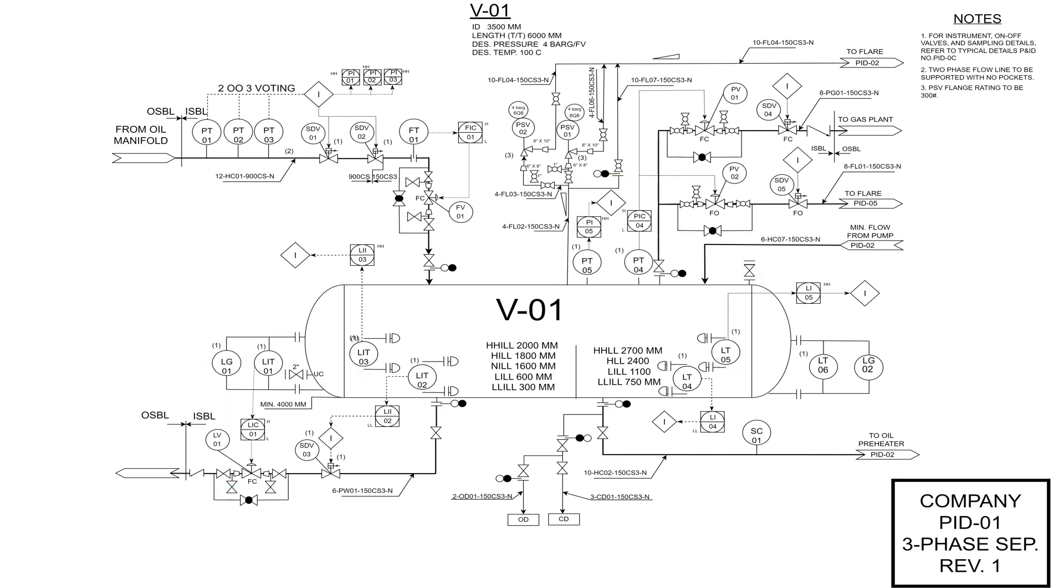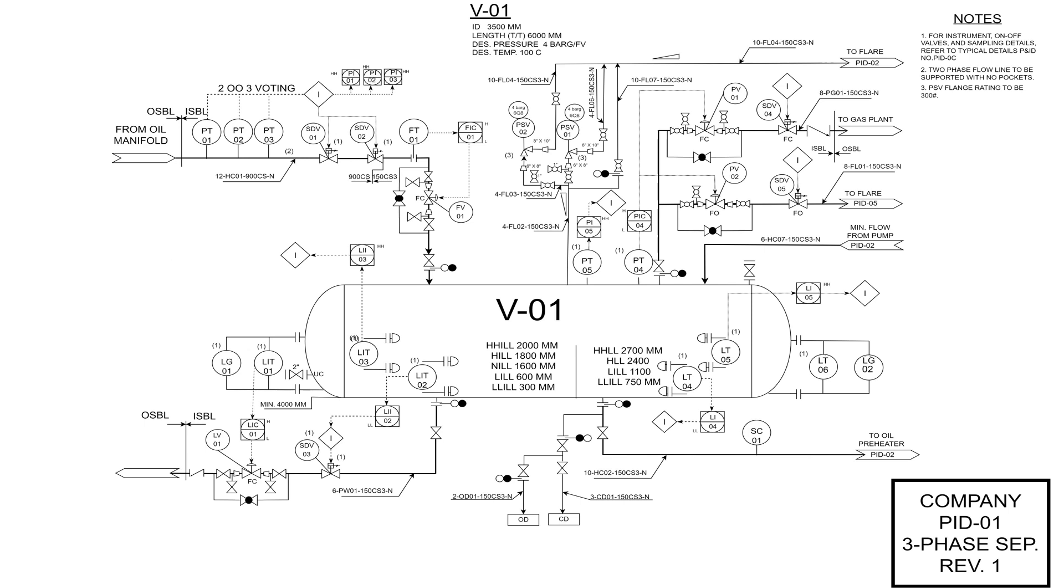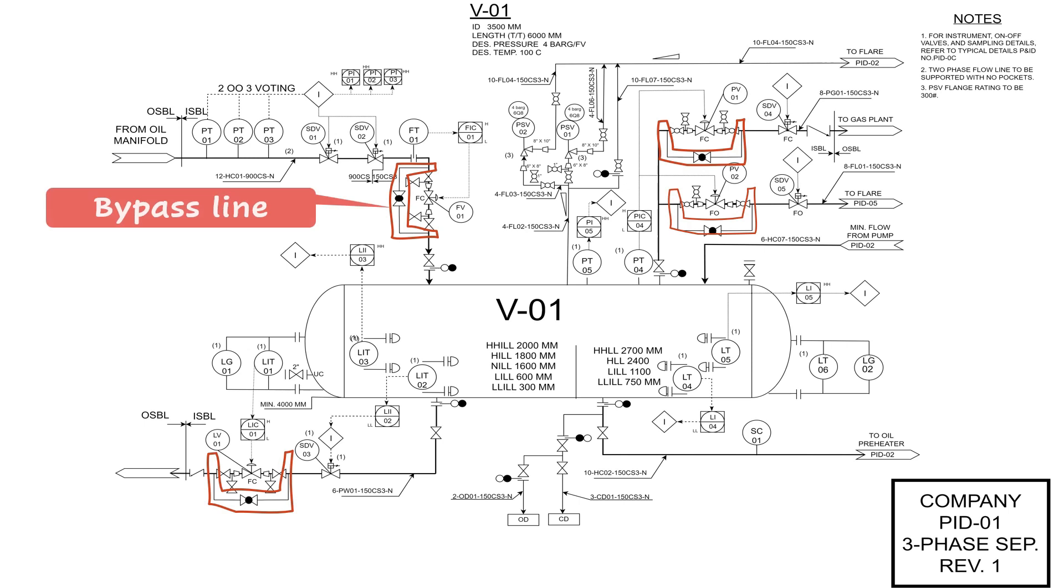Needless to say, not just main process streams are shown as in the case of the PFD, but we should show all lines. For example, a control valve would have a bypass line in case it's out of service, and we want to operate it with a manual globe valve until it's back to service.